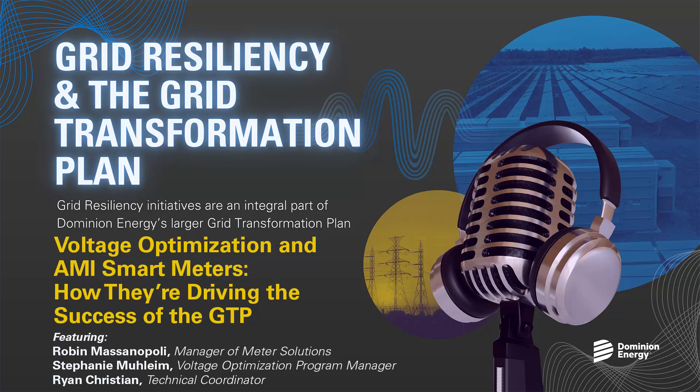Thank you, Robin. Could you just very quickly give us the relationship between AMI smart meters and voltage optimization? Absolutely. The smart meters collect voltage information at each and every premise — each and every home or business. We're currently collecting a voltage reading every 15 minutes. That voltage data is passed over to the voltage optimization team, who can do analysis on the data and determine where we have customers that need line work done in order to bring their voltage into compliance or into the bandwidth we want the voltage to be in. Once we get everybody within that bandwidth on a circuit, we can lower the voltage going to the entire circuit, which is where the money savings starts.